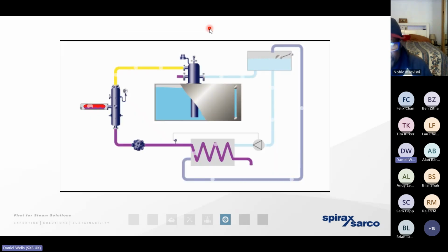In the boiler house itself, that hot water that we need to purge or blow down from the boiler on a daily basis, that high temperature hot water that's leaving the boiler, as it depressurizes and flashes off from the flash vessel, well, that steam can be diverted back to another heat sink, such as the hot well. In other words, if we can identify a heat sink that we can direct that flash steam to, it's free energy. The boiler doesn't have to work as hard, and the cost of steam, cost of gas, and the carbon emissions are going to be significantly reduced.